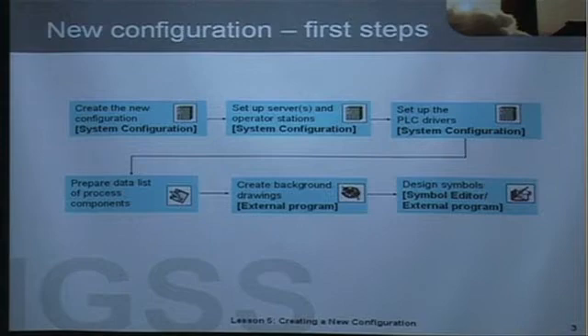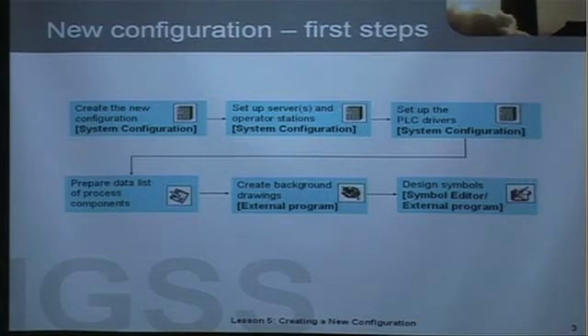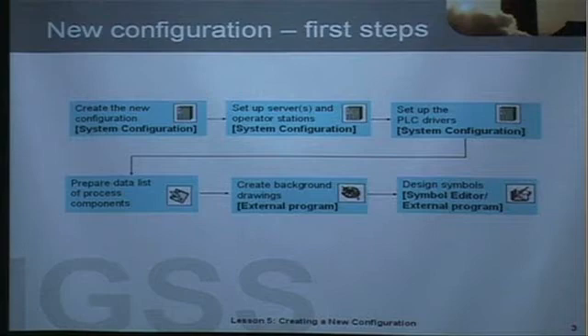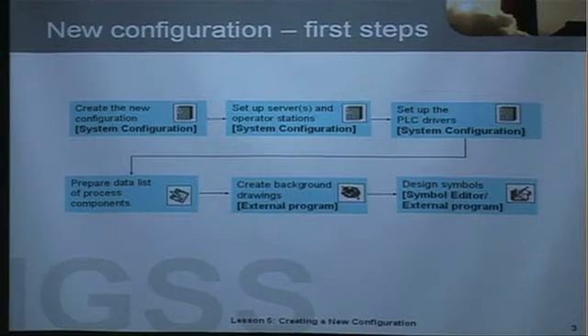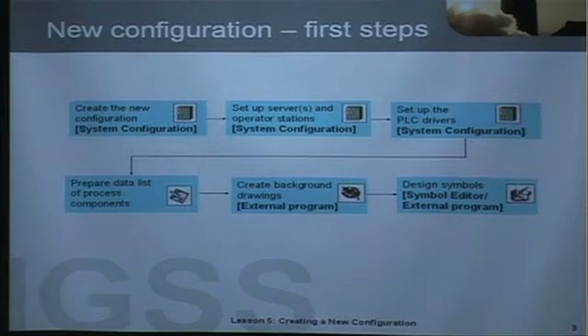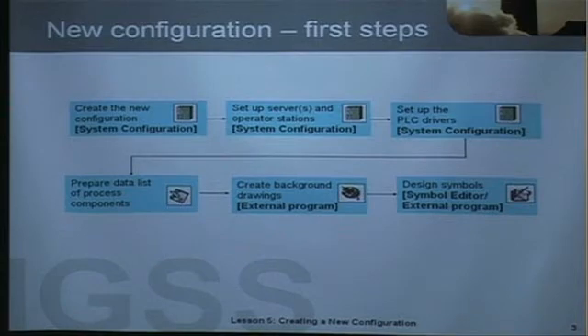When you create a new configuration you must go through this flowchart. First, you create the new configuration in the system configuration module. The next step is to set up the servers and operator stations in a multi-user system. Then you select and set up the PLC drivers and PLCs in system configuration. At this point you must have a data list with all the PLC addresses of the process components, otherwise you must prepare it at this stage.